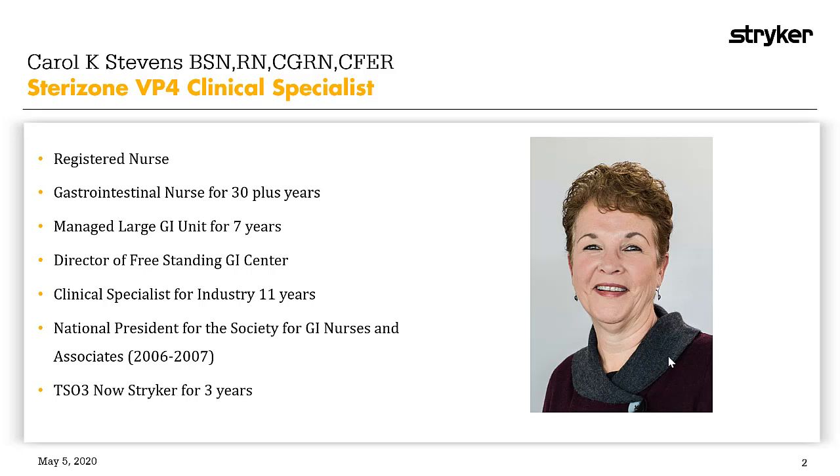I had read there was discussion by Dr. William Rutala that the Spaulding classification may need to be revisited. The proposed changes would affect the critical classification category — it should include items that directly or secondarily enter sterile tissue or the vascular system, like bronchoscopes, cystoscopes, and duodenoscopes. These items should be sterilized. What an opportunity, I thought, to change outcomes for our veterans and all patients. I researched what was available in the market and was excited to find the Sterizone VP4, an innovative technology with dual sterilants — 50% hydrogen peroxide and a small amount of ozone — that could sterilize a specific multi-channel flexible endoscope. I was determined as a patient advocate to make sure a sterile scope would be available for all patients needing an endoscopic procedure, including my husband.